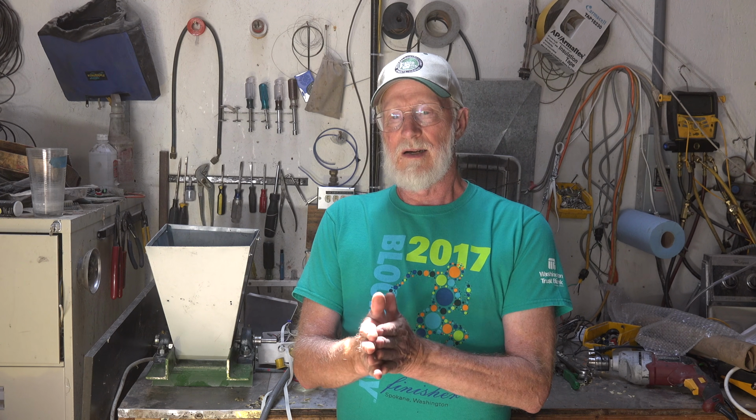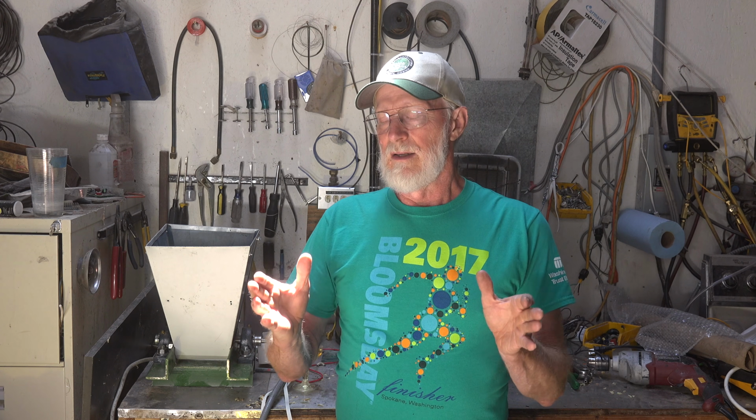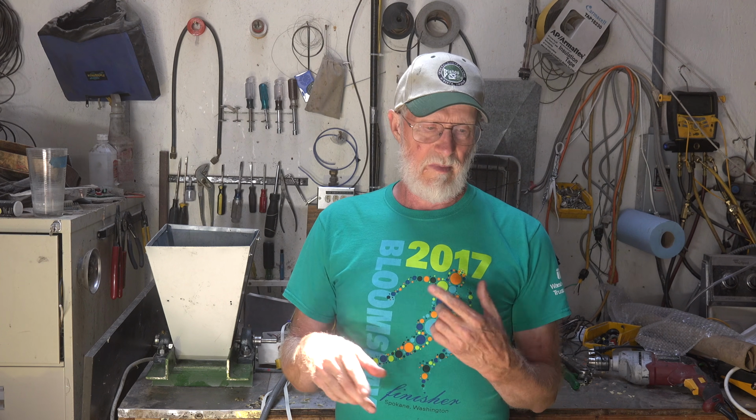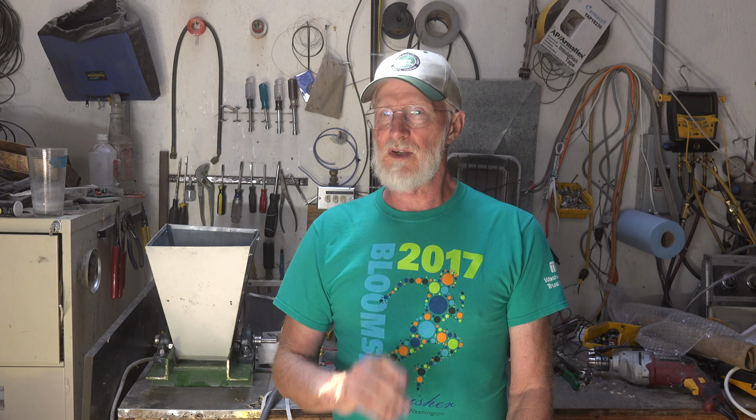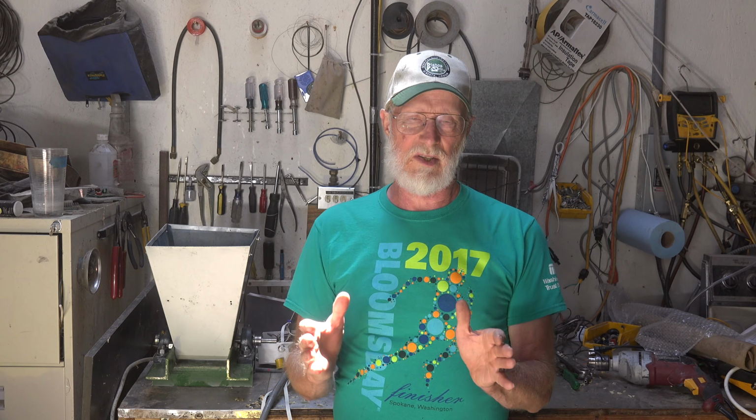So if I'm operating a refrigeration machine and I'm using the lubricating oil to ease the movement of parts and move away heat, those are the two things it does, then if it mixes with the refrigerant when the refrigerant's a liquid, that makes it a lot easier to get it to come back to the compressor. Because if it just pumped out of the compressor, then all the oil would be out in the system and the compressor would dry out and it would destroy the compressor. So we have various ways of getting oil moving through this system.